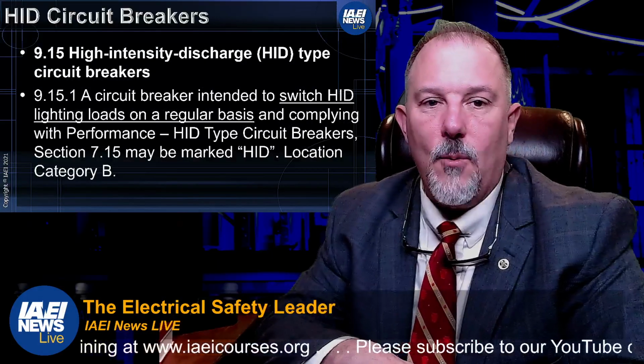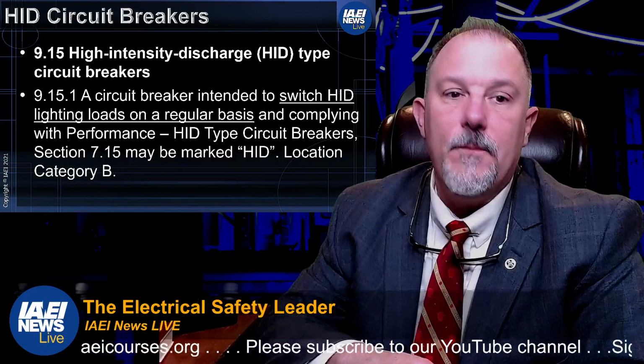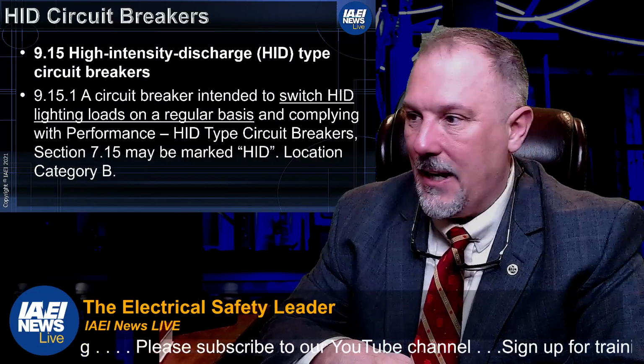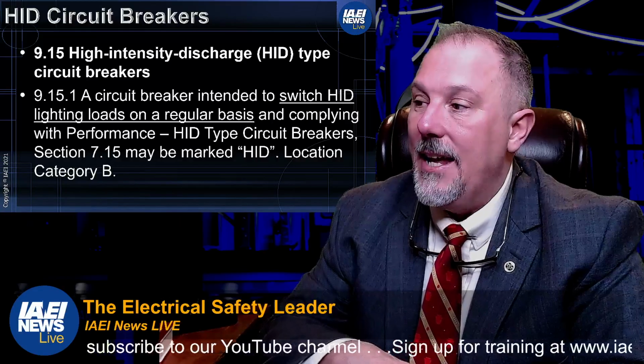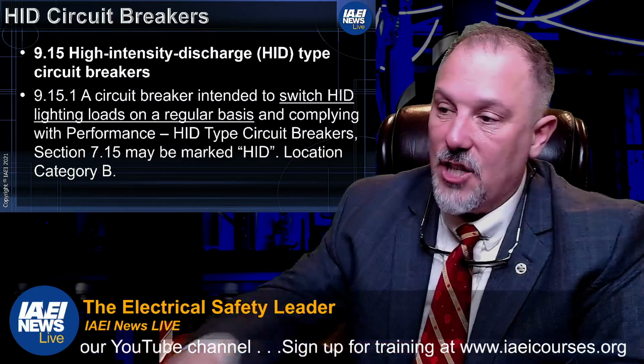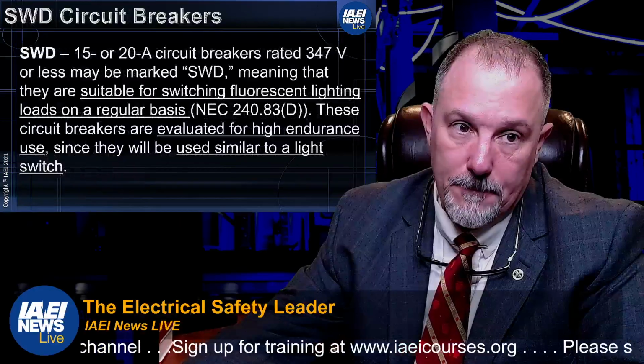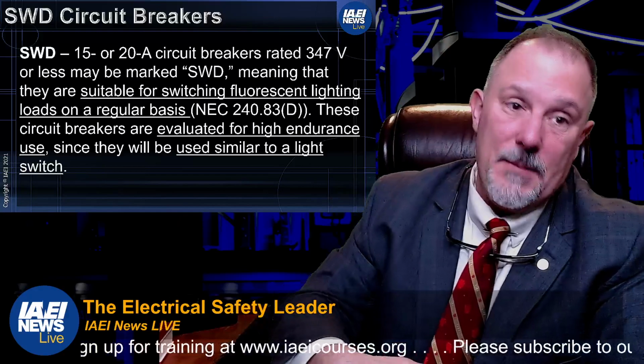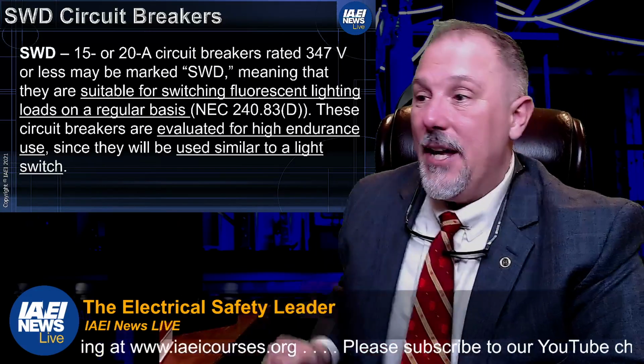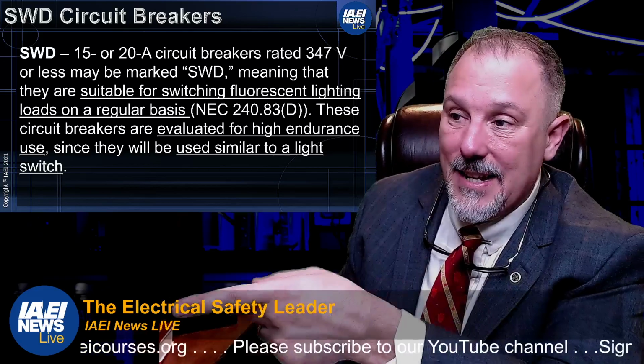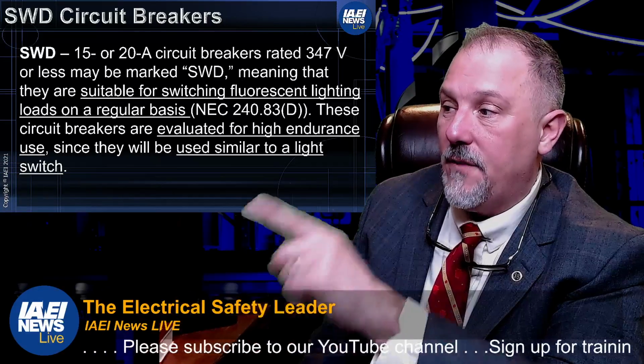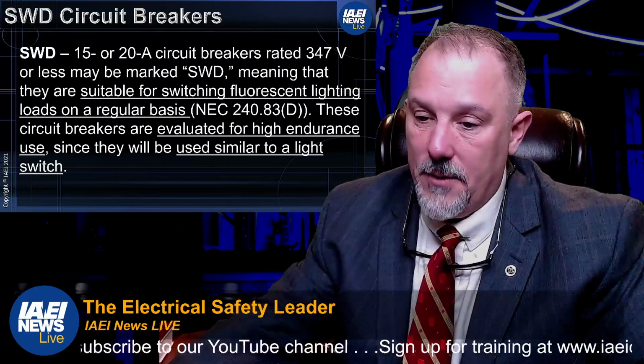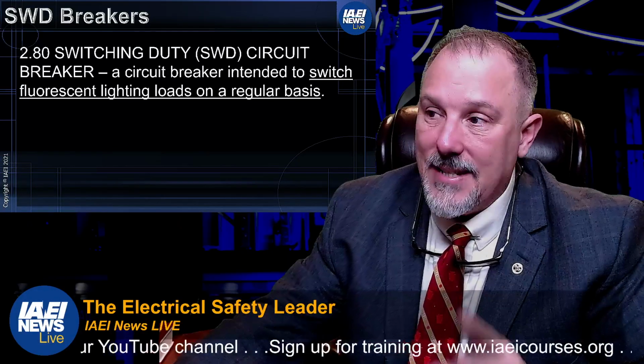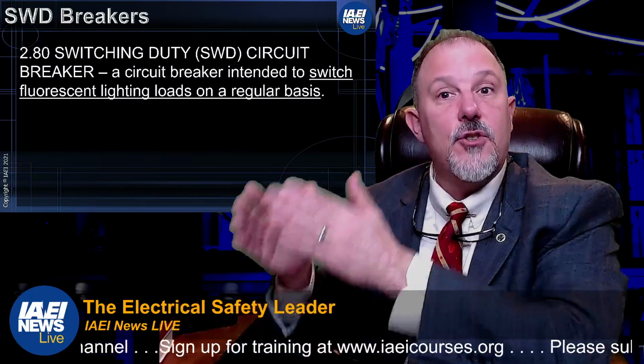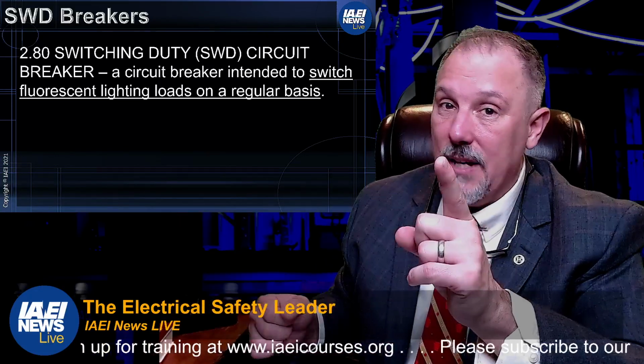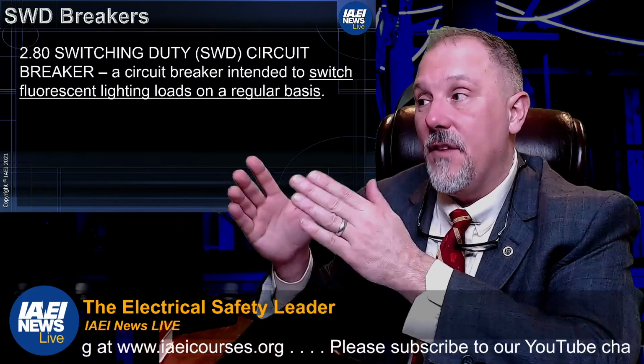Now in section 9.15.1, it says a circuit breaker intended to switch HID lighting loads on a regular basis and complying with the performance requirements for HID type circuit breakers may be marked HID location category B. Now, what about these devices? SWD, we saw those a lot on circuit breakers, right? SWD, suitable for switching fluorescent lighting loads on a regular basis. These circuit breakers are evaluated for high endurance use since they will be used similar to a light switch. So SWD is good for fluorescent. HID can be used on HID or fluorescent, but if you're using SWD, you can use those on fluorescent lights.